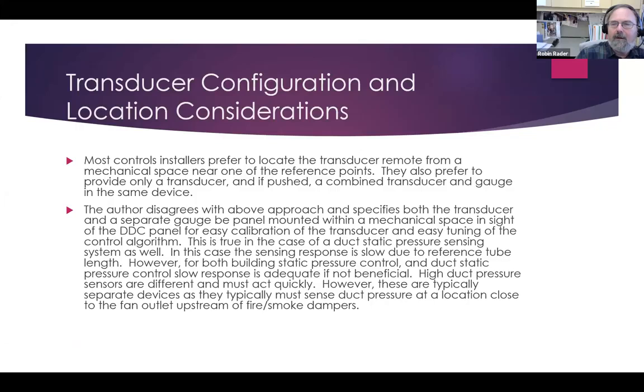Controls people tend to like to have the transducer located by one of the reference points. If left to their own devices, they'll put that transducer out in the ceiling space somewhere. In my opinion, this is a bad idea. I want to have the transducers where I can get to them, calibrate them, and look at things.